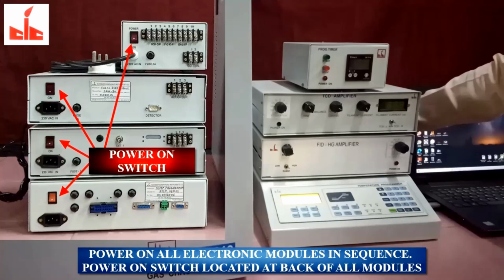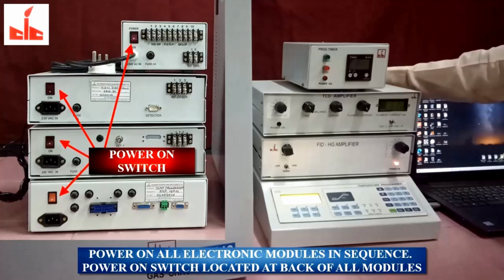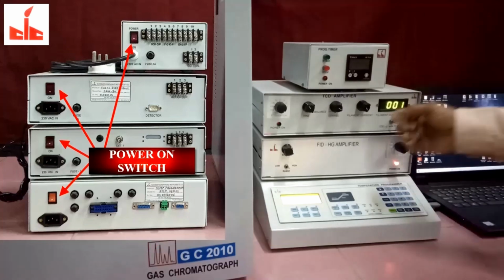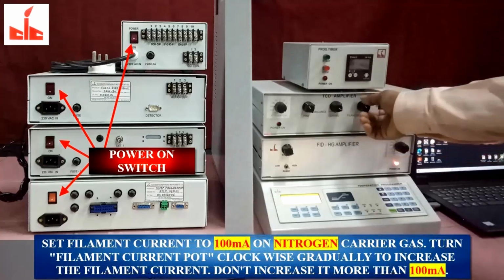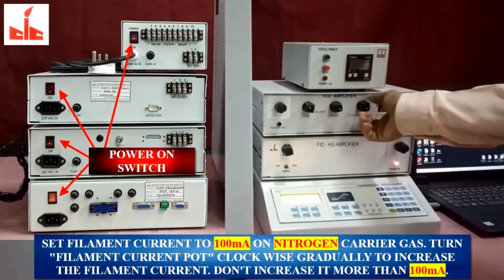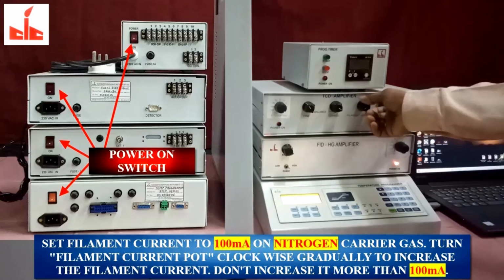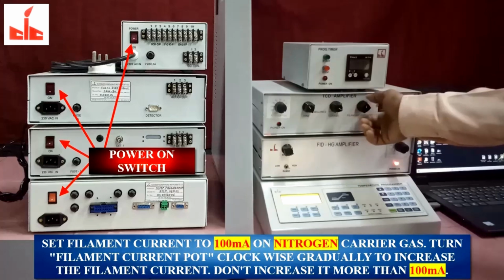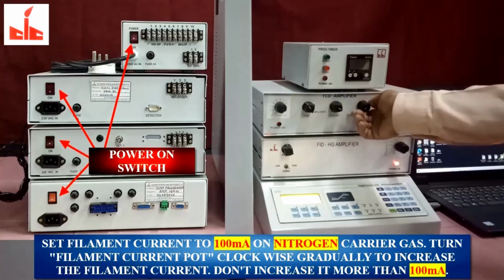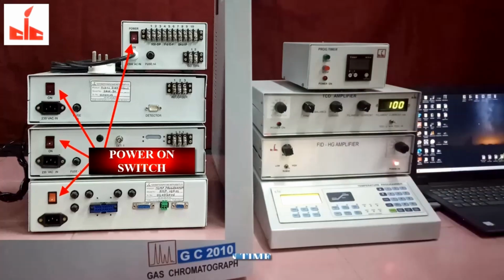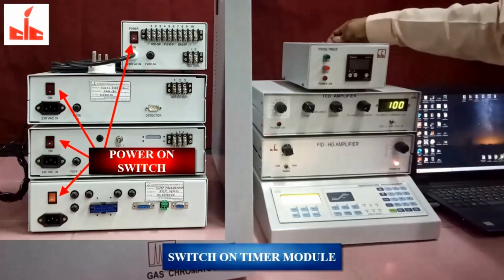First switch on the temperature controller module. Then switch on FID amplifier module. Then switch on TCD amplifier module. Set the filament current to 100 mA on nitrogen carrier gas. Turn filament current pot clockwise gradually, to increase the filament current. Don't increase it more than 100 mA. Switch on the timer module.